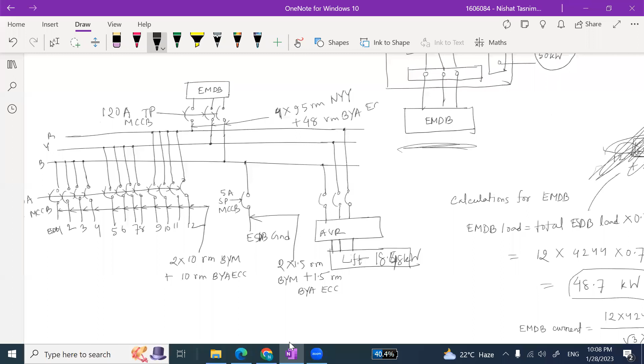And for 120 ampere we use a 95 RM cable. So this will be 4, because 4 wires are going: 3 for red, yellow, blue, and 1 for neutral. 4 into 95 RM NYY plus. Now when the current is really high, for example 120 ampere, we do not need to use the same size for the ECC cable. We can use a half-size ECC cable. So we can use 48 RM BYA ECC. So for high currents, we can make the ECC cable size half.